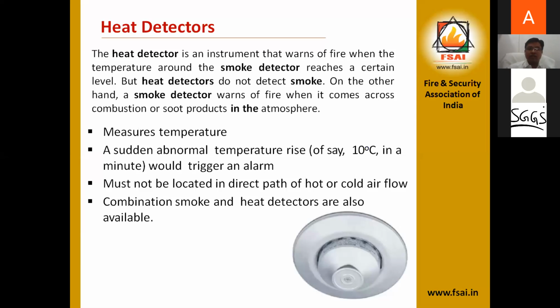On the other hand, a smoke detector warns of fire when it comes across combustion or soot products in the atmosphere. What do heat detectors do? Heat detectors measure the temperature. A sudden abnormal temperature rise, like say 10 degrees Celsius in a minute, would trigger an alarm. They must not be located in the direct path of hot or cold air flow. Combinations of smoke and heat detectors are also available in the market. So we have a choice to provide separate heat detectors or smoke detectors, or a single unit which can detect smoke and heat and inform us when any fire occurs.